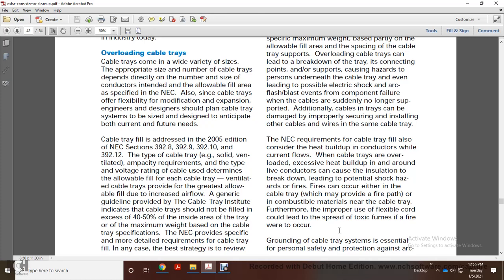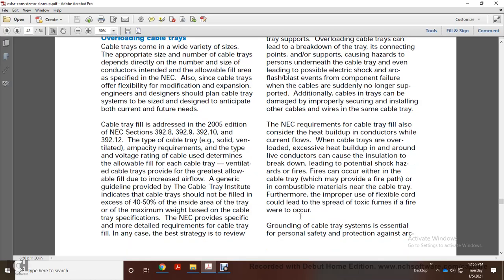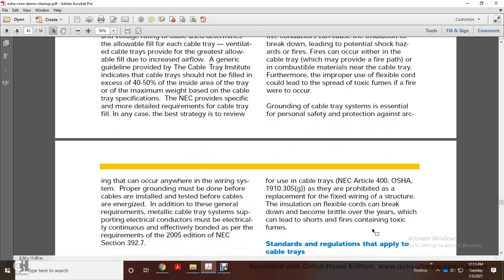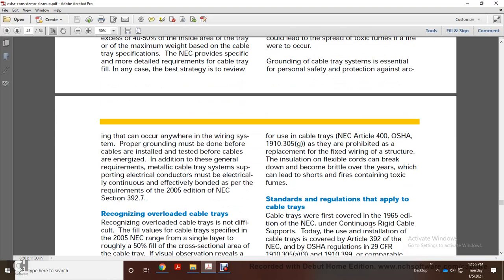The fire can occur either in the cable tray, which provides a fire path, or in combustible material near the cable tray. Further, improper use of flexible cord could lead to the spread of toxic flame, fumes and fire. Grounding cable trays is essential for personal protection against arcing in the wiring system. Proper grounding must be done and tested before cables may be energized.